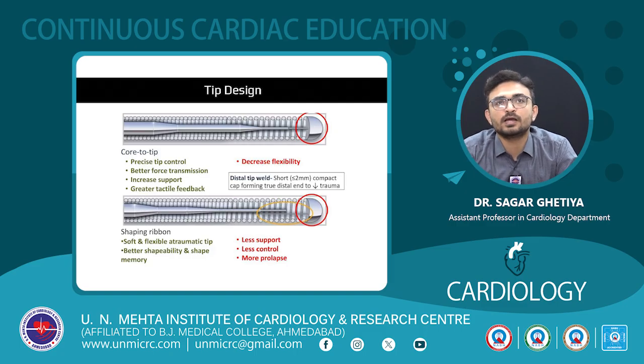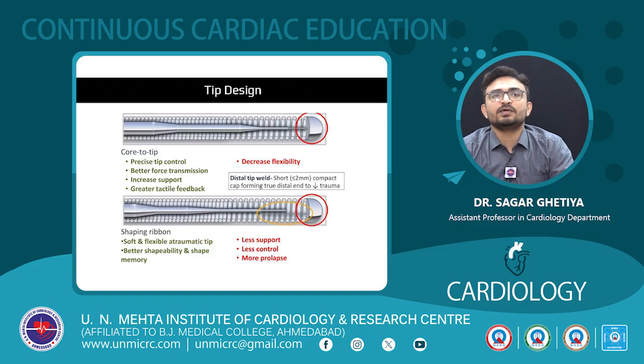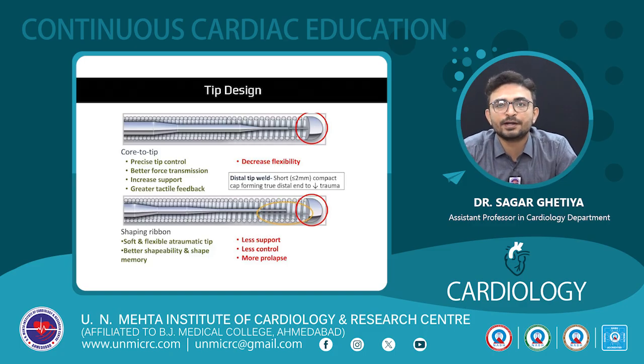With this design, we have precise tip control, better force transmission, and increased support with better tactile feedback. But there will be decreased flexibility. While with the shaping ribbon design, there will be an atraumatic flexible tip with better shapeability and shape memory. But support and control will be less, with more chances of prolapse.